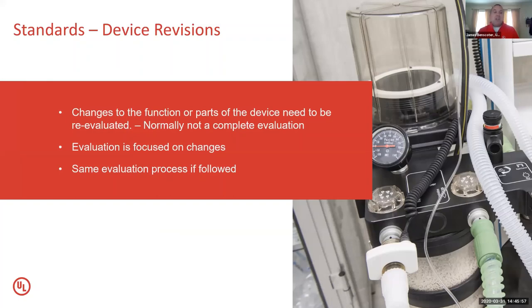So this means the manufacturer is going to have to validate that the parts they're choosing as replacements still make the device as safe and effective as it originally was. The EUA is just saying you don't have to submit it to us and ask for permission formally to go through the full review, but you need to have done your, I'll call it due diligence, and done your relevant evaluation to make sure it happens.